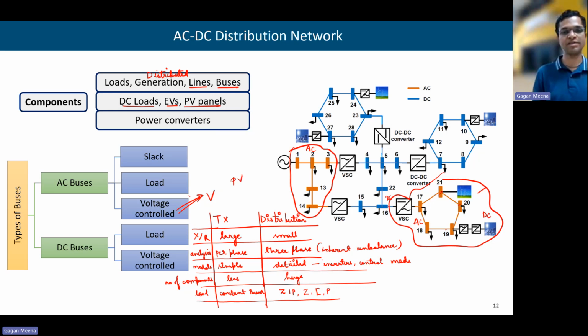There are PV buses where P and V are both specified. These are the generator buses, where the generator generates at a specified power at a specified voltage. Voltage controlled buses can also be buses where capacitors are connected, or any reactive power compensation device is connected.